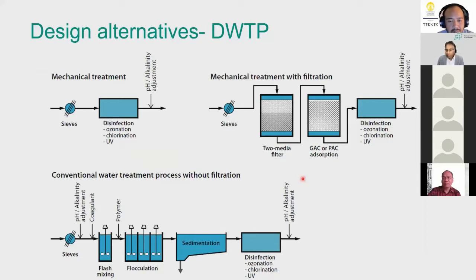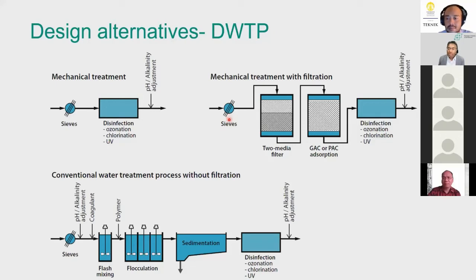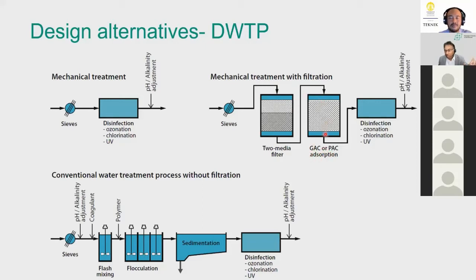A figure of design alternatives is presented. The simplest option is mechanical treatment with a screen followed by disinfection, typically used for groundwater. For surface water from a lake that is relatively clean with few particles, water can be sent through a two-media filter — two types of sand of different sizes — then through granular or powder activated carbon to remove remaining organic matter, followed by disinfection.